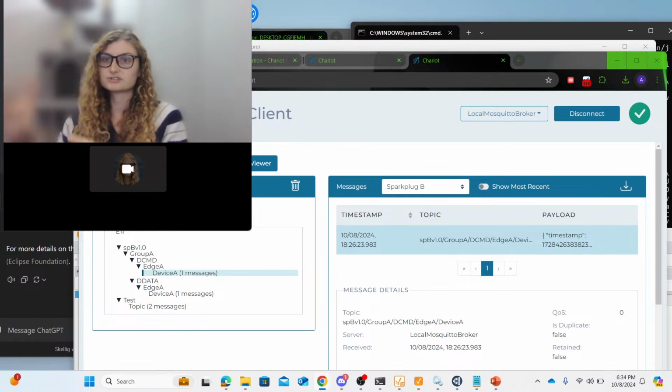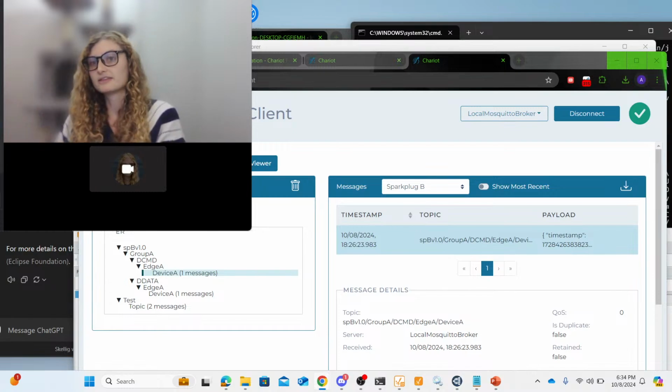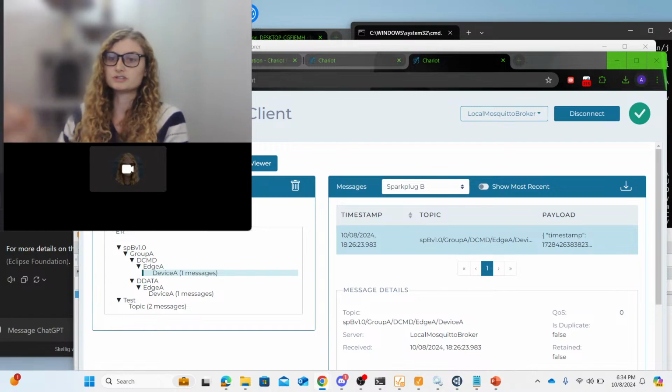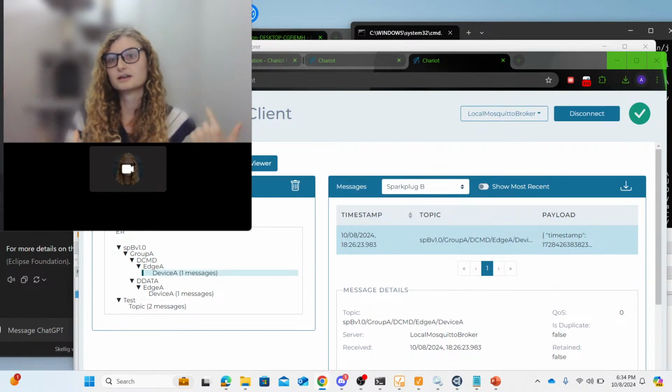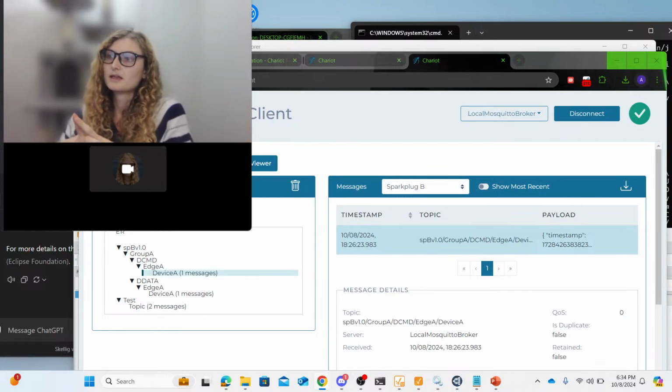At least use Ignition to help model all that data into UDTs. And then, with those modules, you can get that data sent out over MQTT into your broker, where your master Ignition system, which is probably going to be your SCADA, so to speak, can then communicate with and control that bioreactor through SparkPlug.